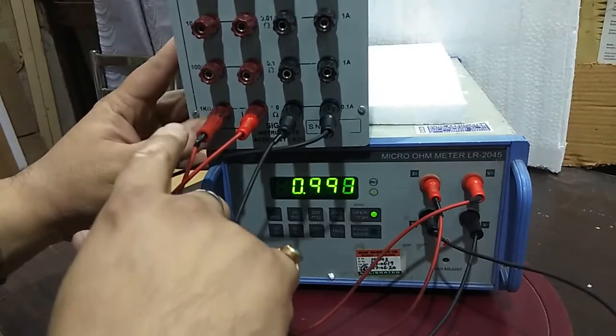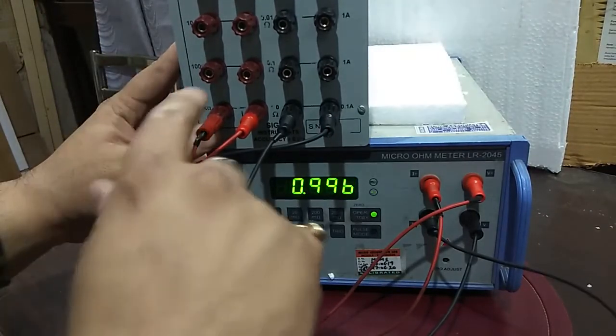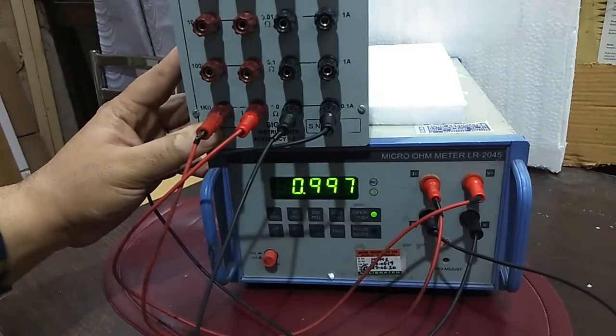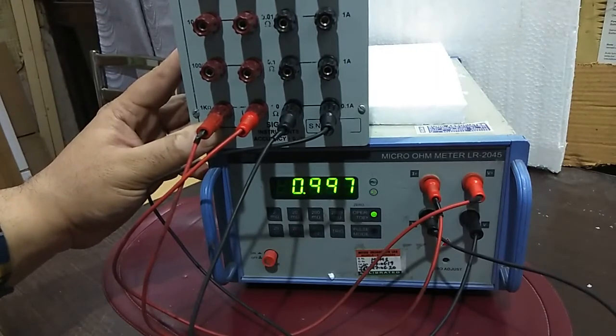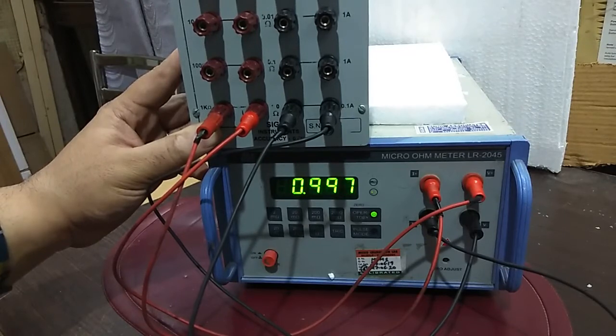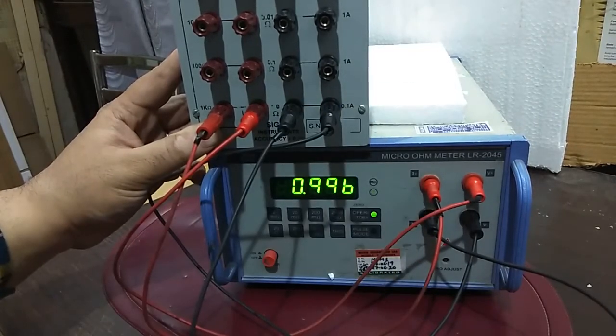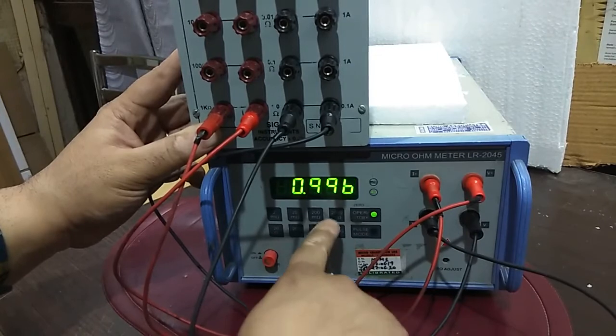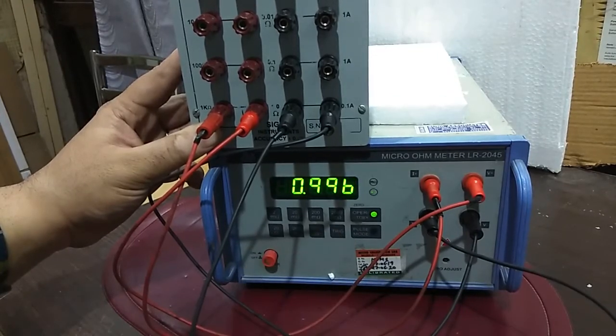You have to use a four wire system. The four wire system must be used for measuring the lower resistance. Otherwise the contact resistance starts and the results will go out. I will be showing you all the things in this part only.